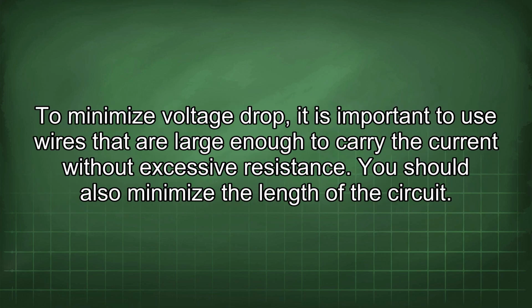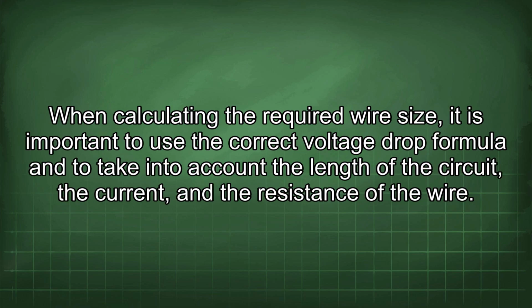To minimize voltage drop, it is important to use wires that are large enough to carry the current without excessive resistance. You should also minimize the length of the circuit. When calculating the required wire size, it is important to use the correct voltage drop formula and to take into account the length of the circuit, the current, and the resistance of the wire.